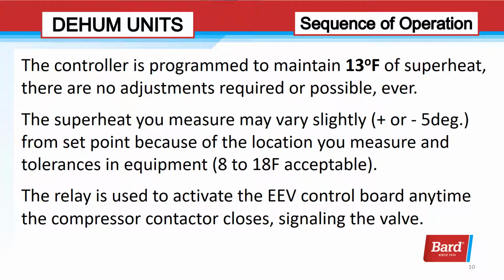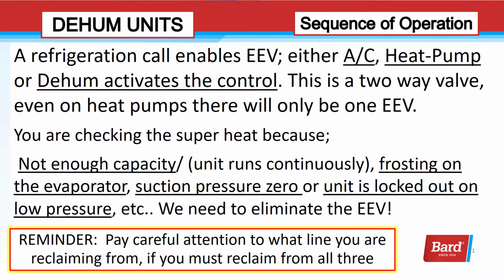The relay is used to activate the EEV control board anytime the compressor contactor closes, signaling the valve to go into operation. A refrigerant call enables the EEV. Either air conditioning, heat pump, or dehumidification activates the control. And this is a two-way valve. Even on heat pumps, there will only be one EEV.